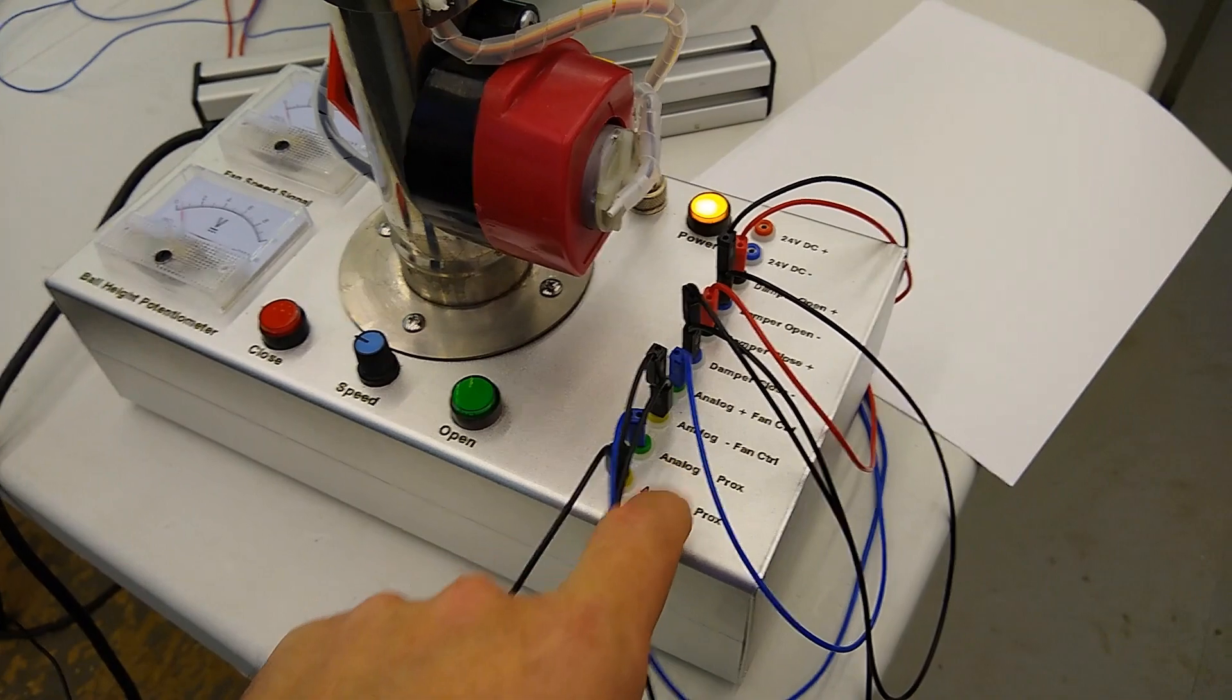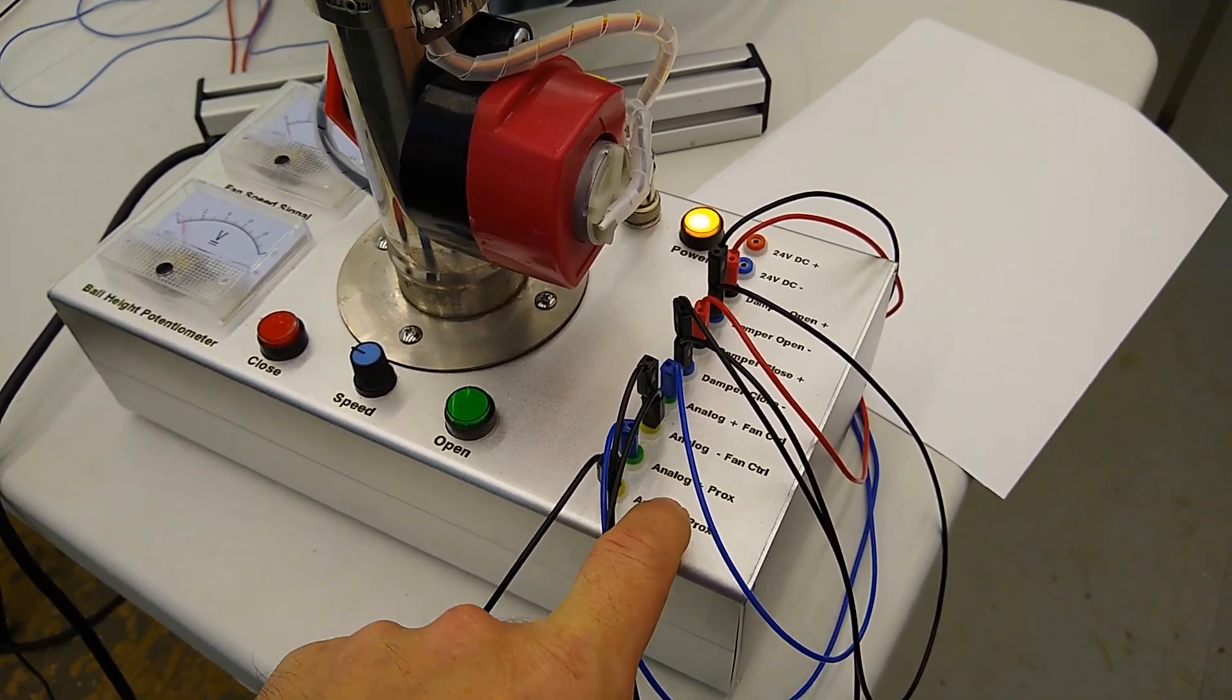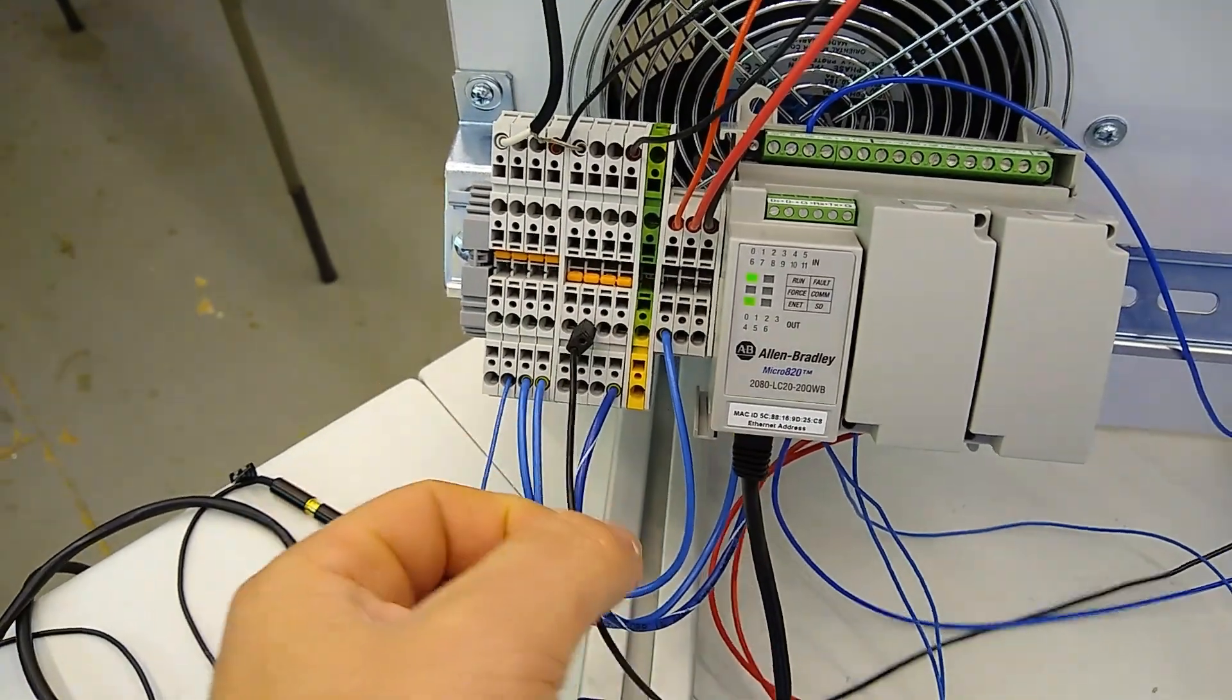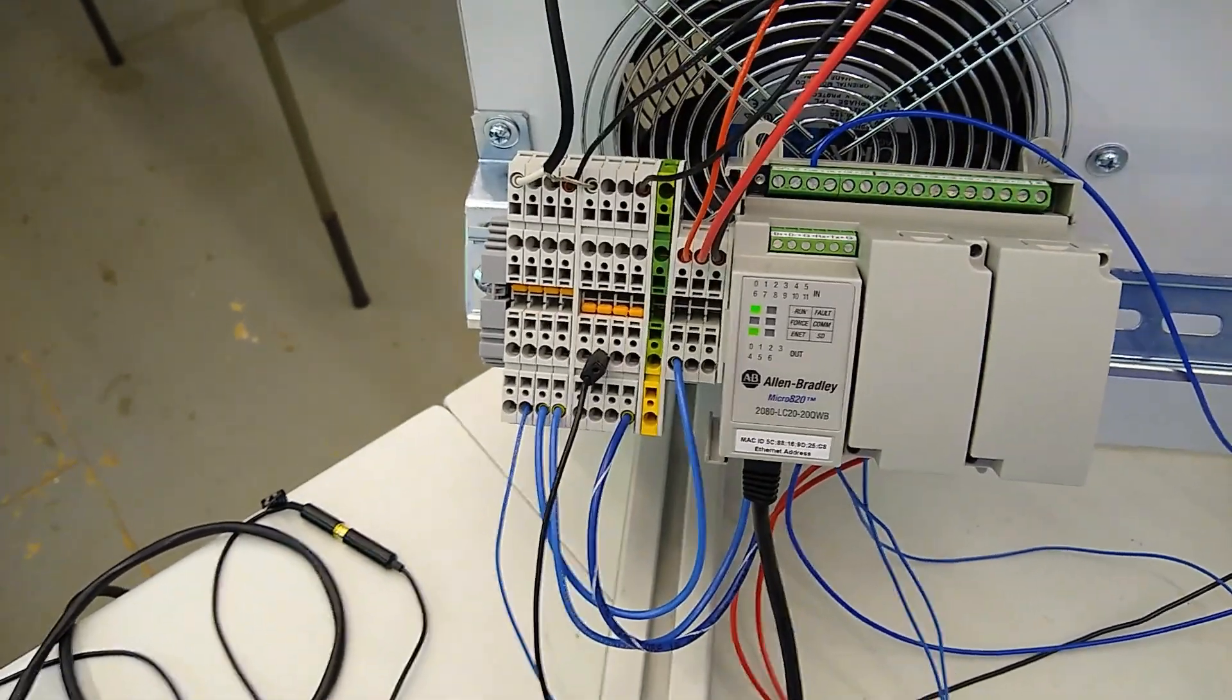So on each point you have a plus and a minus and we're going to jumper all of the minuses together and then it's going to go along to our right set of terminal blocks which is the zero volt of our 24 volt power supply.